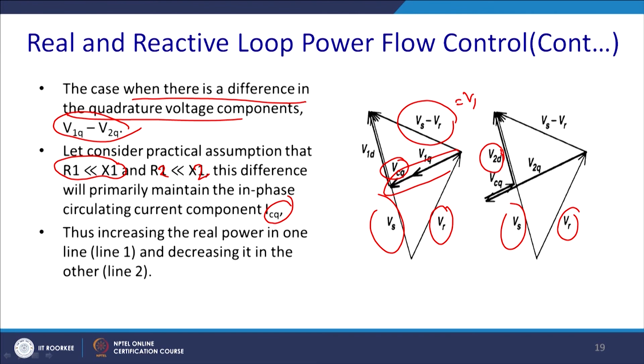So, due to that what will happen? Conduction will take place in different lines in a different manner. For this reason we need to compensate it and we try to make this value equal, and you see that we have eliminated the component CQ. In case there is a difference in the in phase component of the voltage component VD1 and VD2, the difference will primarily maintain the in phase circulating current component CD. We can compensate if this V1Q and V2Q are the same, and thus the change in reactive current flow will balance, but there will be a difference of the real power flow.